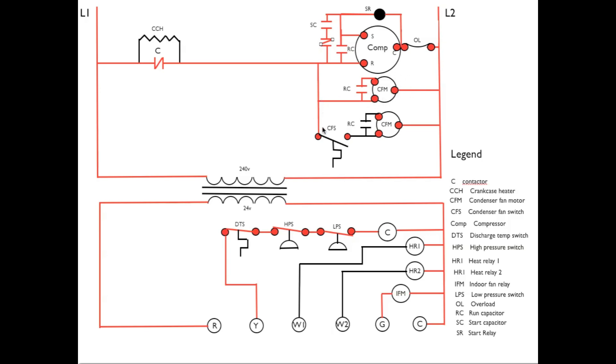Now, in this case, we're assuming CFS, or condenser fan switch, is open so the second condenser fan motor does not come on. Now here it gets a little more complicated. We're going up to the compressor running through the run capacitor to start.